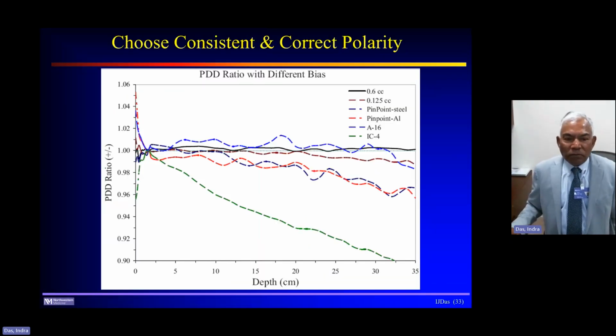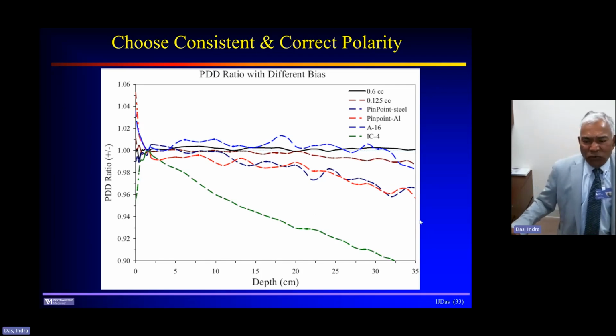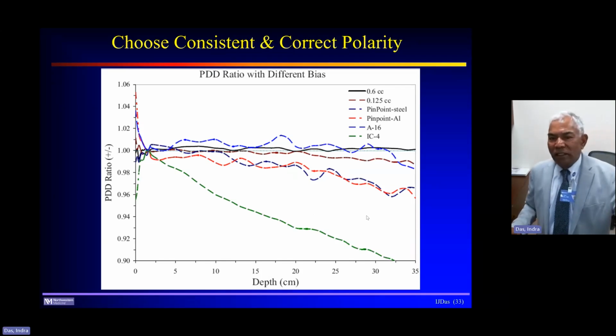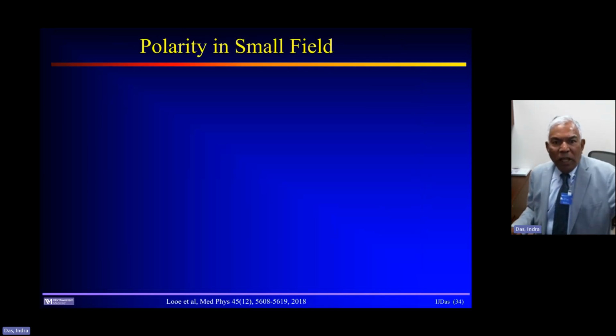Another thing is the polarity. Most of us don't pay attention to polarity. We just set plus or minus. But if you go through the depth ratios of the PDDs for plus and minus, you can see that some detectors have large differences in the polarity. So that's another problem: you have to be consistent with your measurements, use the proper voltage, proper bias, and go through that.